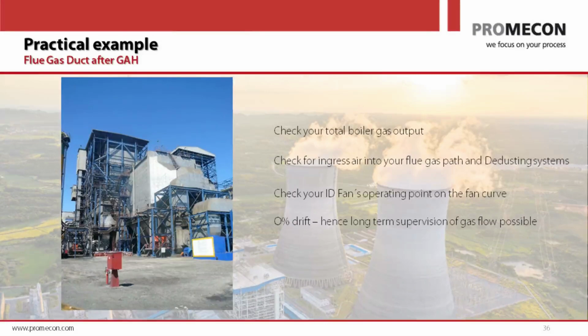Another example that I've not been talking about much, and I'm not sure in how far it is of interest to you, but many power stations also are suffering from back-end gas flows. What are the typical issues? Typical issues would be the flow of boiler flue gas on the left and the right-hand side of the flue gas duct. So you have an A side and a B side. You have two EPs. Is the flow through these two EPs the same? Very often it's not. Very often you have an ID fan, and both ID fans show you the same power rating. They show you basically the same power consumption. But basically the operating point on the fan curve is not identical because one system is different from the other. So one side pulls more gas flow than the other one.